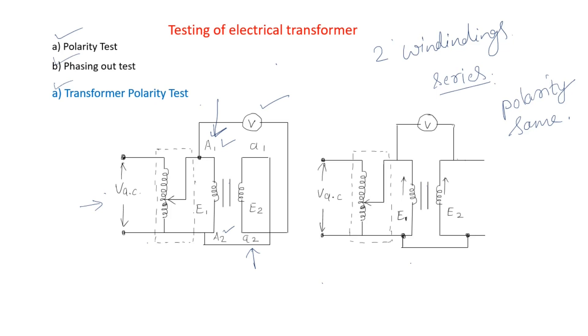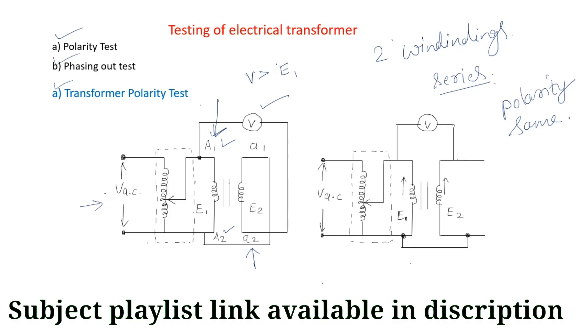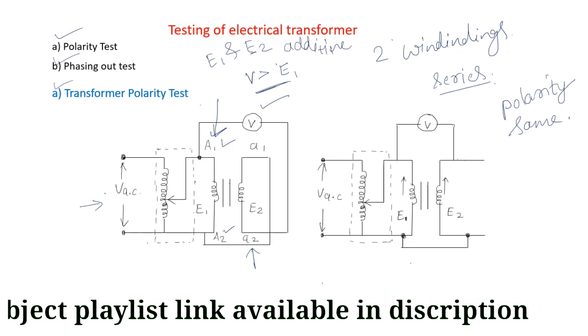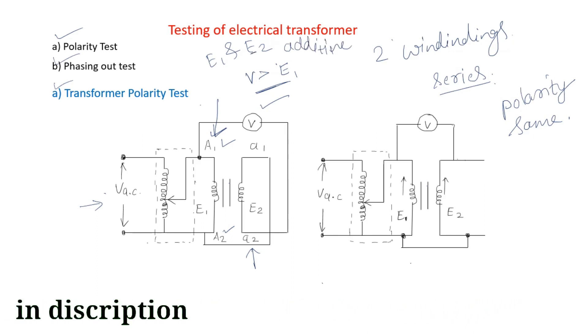The voltage across A1 and a2 is measured by voltmeter V. If V is greater than E1, it clearly indicates that both the EMF induced in A1 and a2 are additive, so assumed polarities are correct. This is what we have assumed - the polarity we assumed is correct.